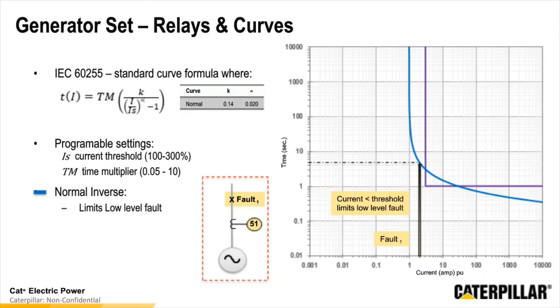There are also curves that are available within the relay set points. So the curves are based off the IEC 60255 standard. You can see the formula here that's used to calculate the curve along with the values that are used. These curves are programmable. You can use a current threshold of 100 to 300%, and that allows us to move that curve horizontally across the axis, or we have a time multiplier that allows us to also move it slightly vertically.